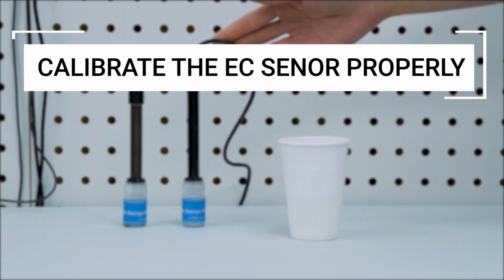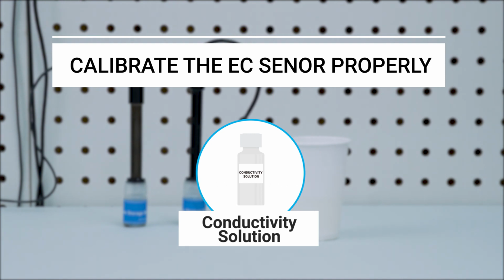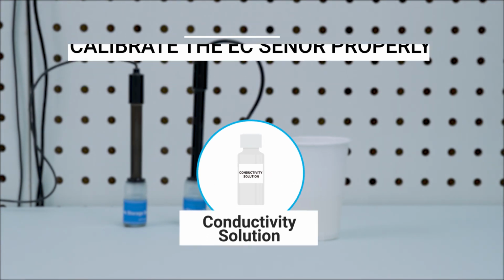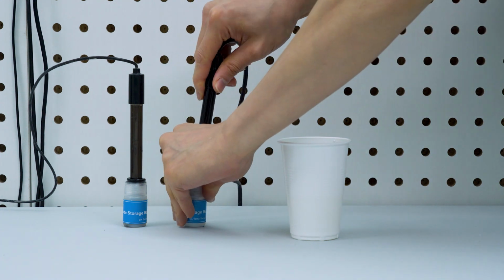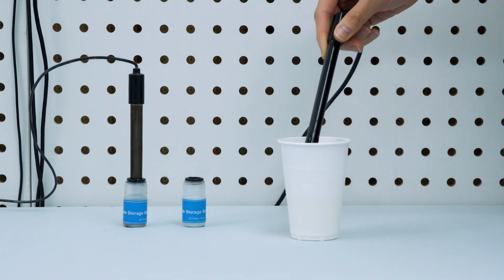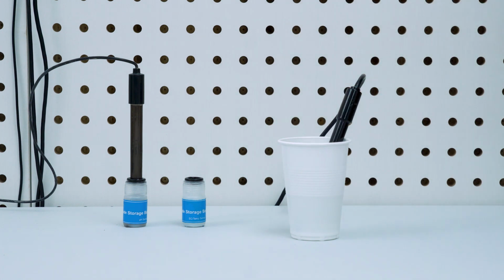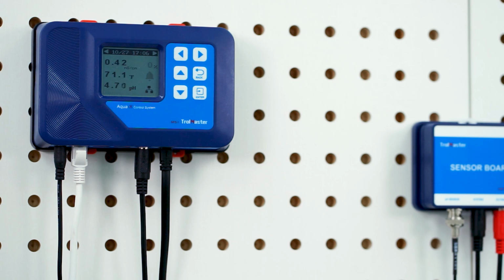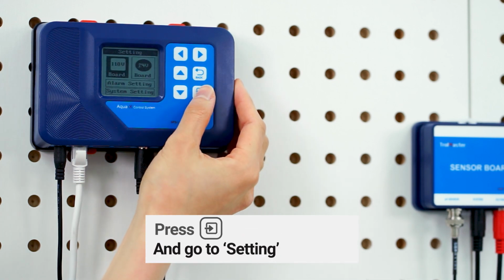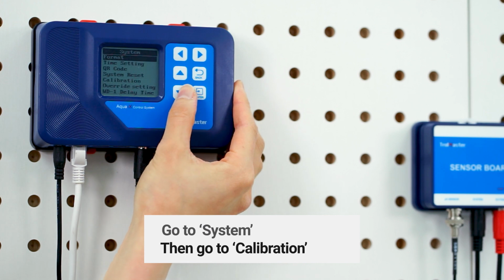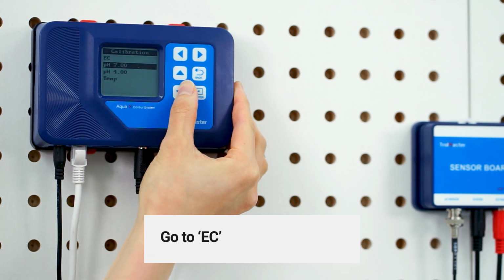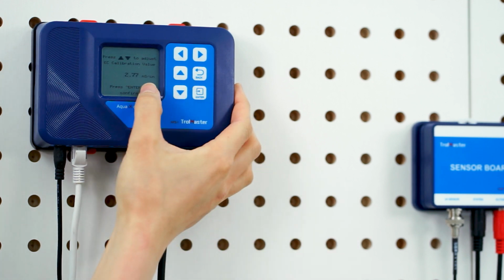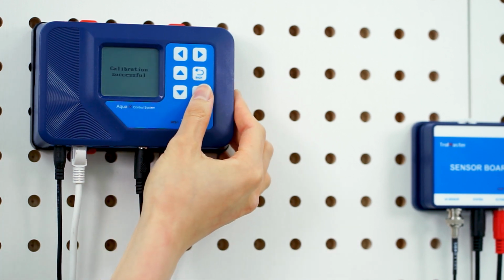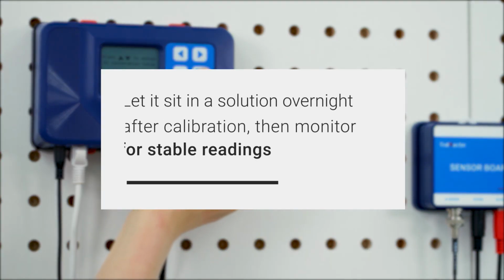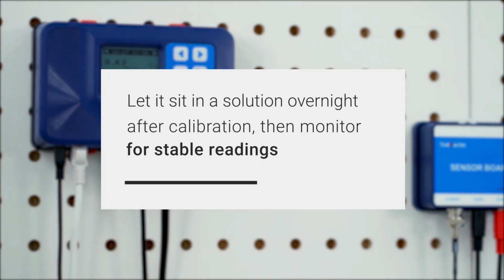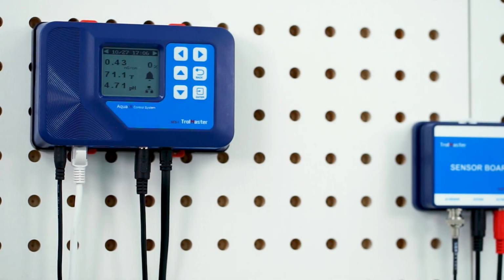To calibrate your EC sensor properly, prepare a bottle of conductivity standard solution. On the main menu of the Aqua-X controller, press the Enter button. Go to Calibration. Then go to the EC menu. Readjust the same value with your EC solution. After calibration, again, let it sit in the solution for 24 hours and see if you can get stable readings.